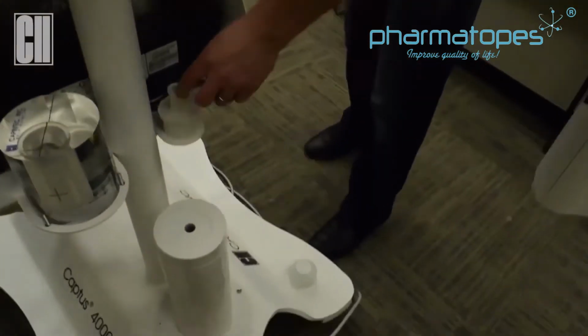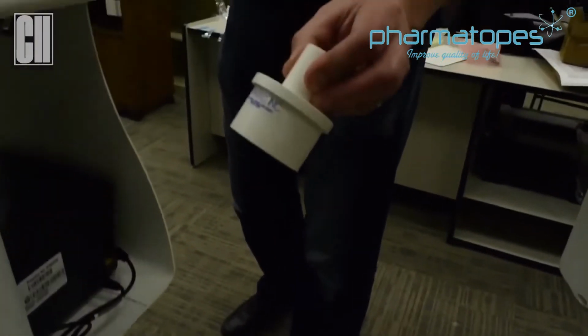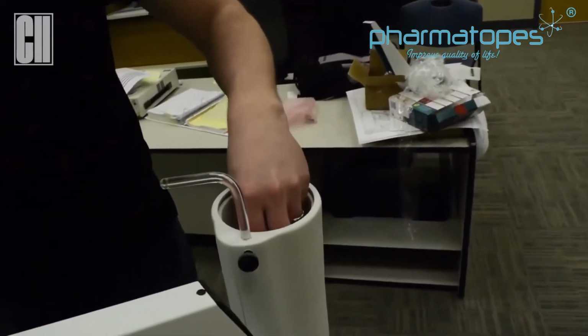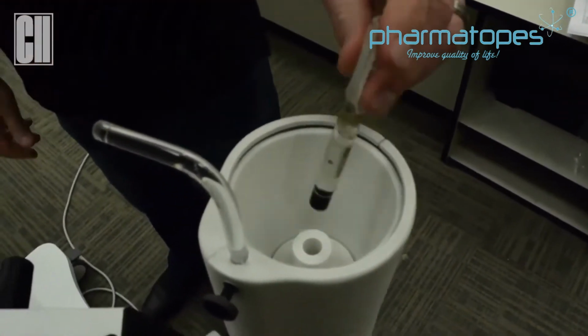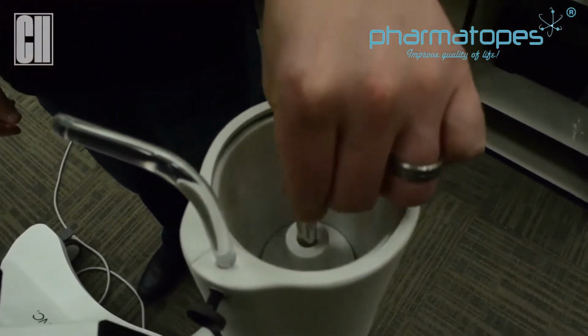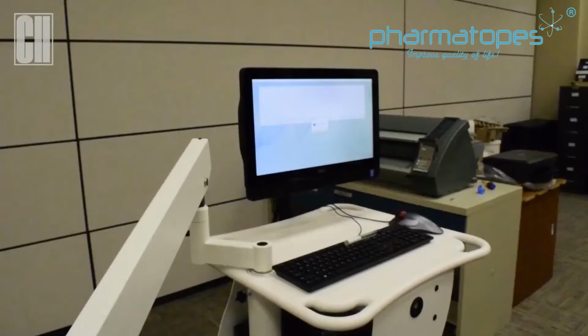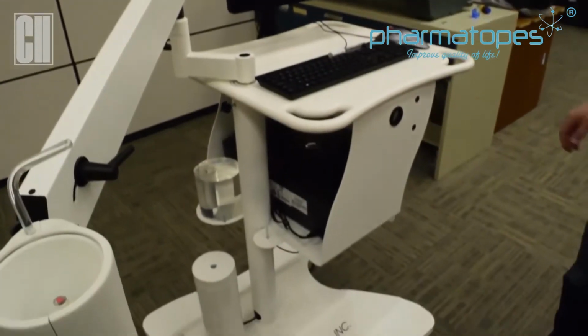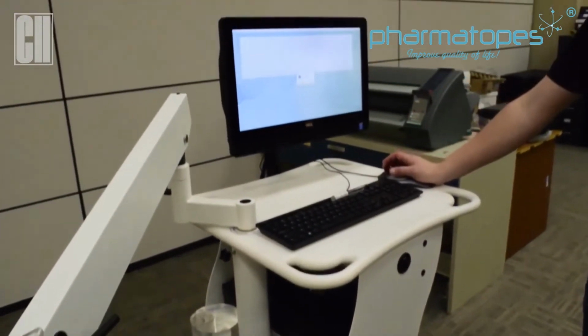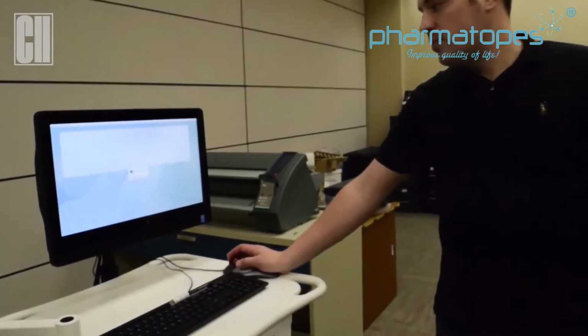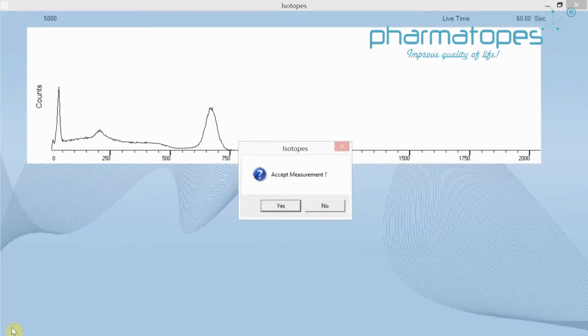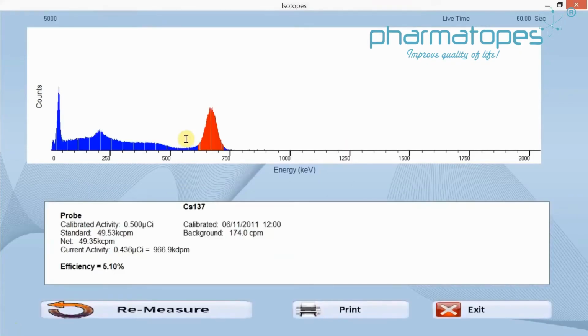So now you'll need your source holder once again for the probe, and we're going to place that into the probe. And now position the cesium source into the probe. Okay. So after we measure the cesium and accept it, we're going to get an efficiency, and the result will be shown there. The result should fall into a 3.17 to 6.33 window.